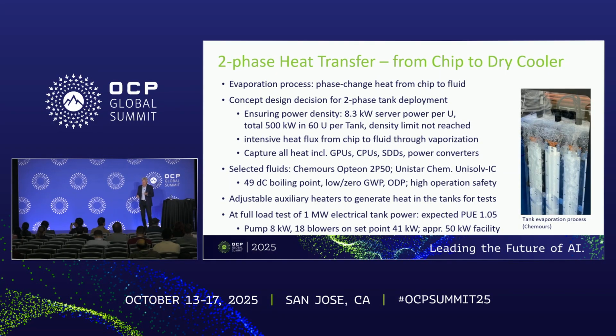The cooling generation always decides how much cooling you can provide on a given space, which defines the IT capacity. So we decided for that megawatt and bring all the hardware into the tank - you see it boiling here, this is a Chemours picture. We work with them for a 49 degree boiling point.